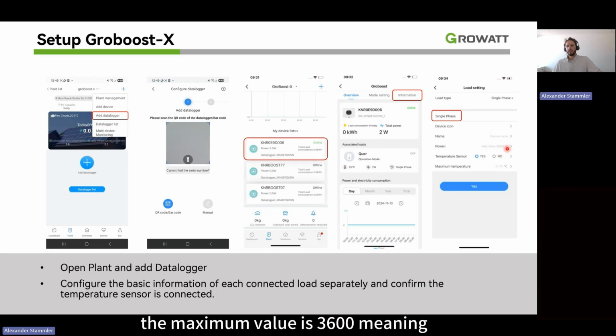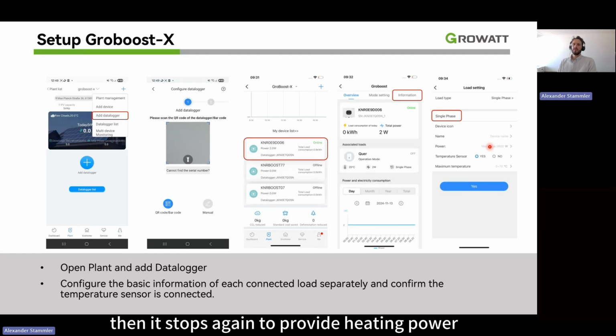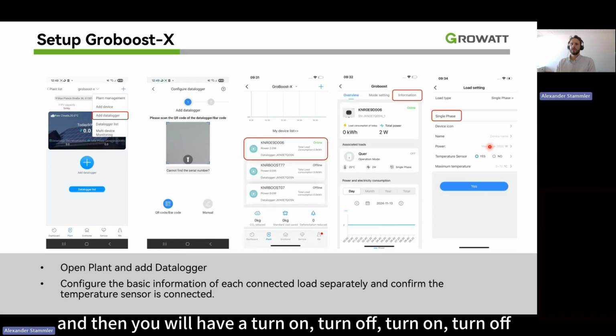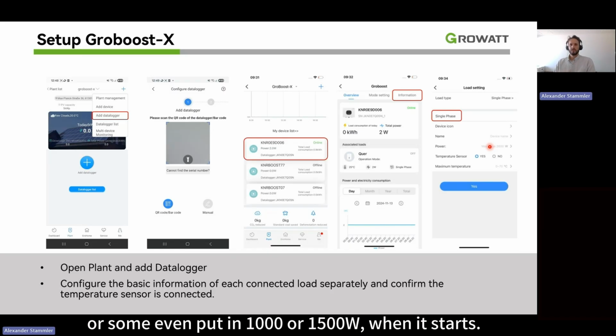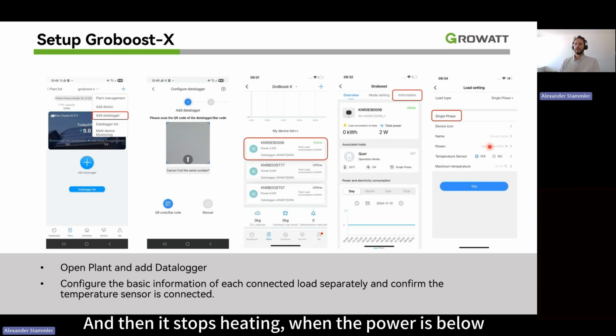And here you can put in the power. The maximum value is 3,600, meaning here you put in the power at which it should start heating. For example, if you have an output of 1 kilowatt into the grid, then it should start heating. It's not recommended to use something like 50 watts because it fluctuates a lot. If it's 50 watts and then it goes under 50 watts, it stops providing heating power again, and then you will have turn on, turn off, turn on, turn off. So it's recommended to use a couple of 100 watts, or some even put in 1,000 or 1,500 watts when it starts, and then it stops heating when the power is below that or when no power is exported anymore.